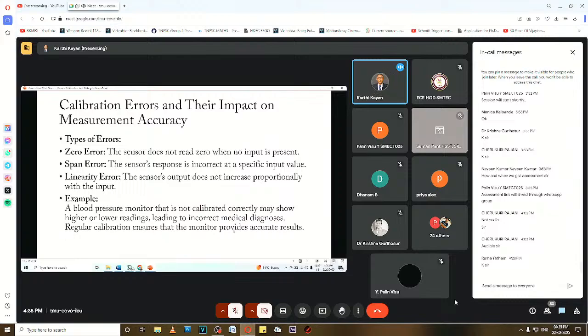Next, span error. Span error is when the sensor's response is incorrect at a specific input value. If you give 5 or 6, it has to show the readings 5 and 6. Particularly, if you take an ammeter or voltmeter, it has to show 5 volt or 10 volt perfectly, 5 amps, 10 amps perfectly. If it doesn't do that, it is a span error. Next, linearity error. The sensor's output doesn't increase proportionally with the input. The sensor's output voltage.